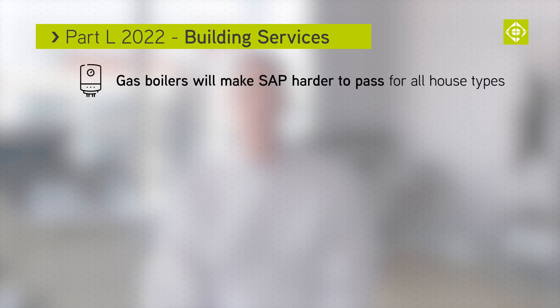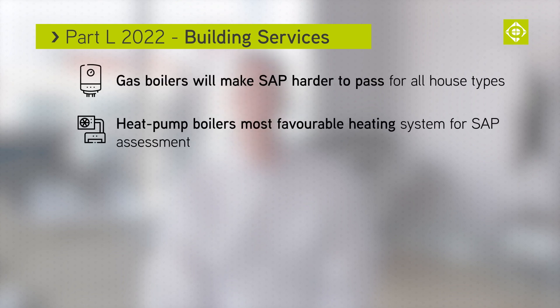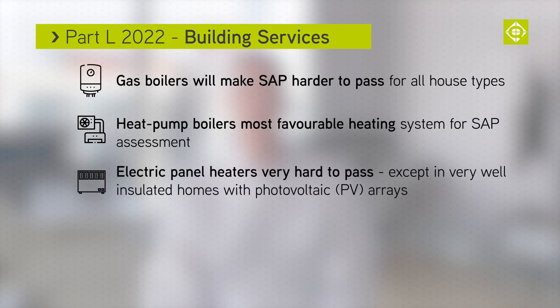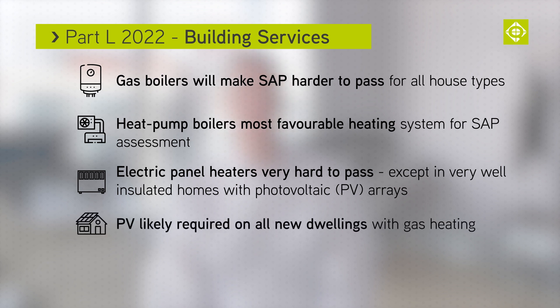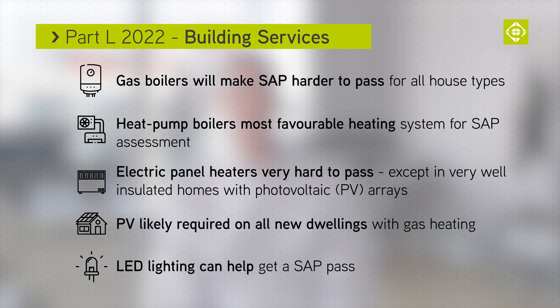Gas boilers will make a SAP assessment harder to pass for all home types. Heat pump boilers will be the most favourable heating systems available for new build dwellings. Electric panel heaters will make it hard to get a pass except in small apartments and very well insulated homes with PV. Photovoltaics, or PV, are likely to be required on all new build schemes which use gas. LED lighting can also help to get a pass.